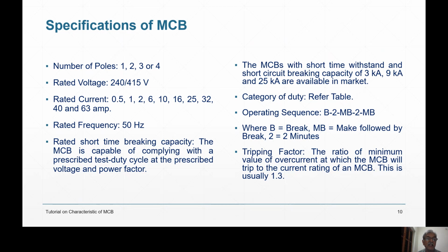Now, rated short time breaking capacity. That is what current it can break without being damaged. And this is known by duty cycle. This duty cycle in Indian standard is specified as B to MB to MB. B is break. That means when you pass a very high current, high current means short circuit current. For a 2 ampere or 6 ampere MCB, I will be passing 3000 ampere of current, and because of that current it will immediately break. Then you have to wait for 2 minutes and then again make.